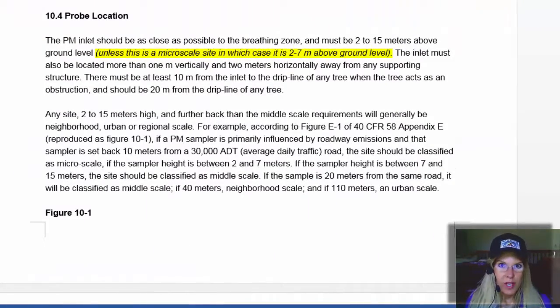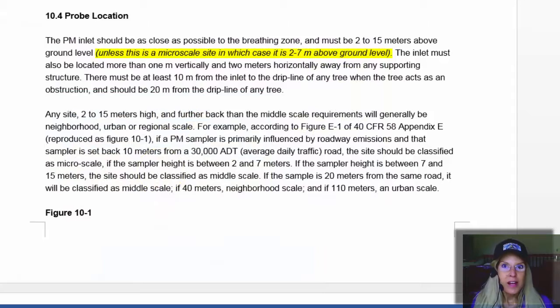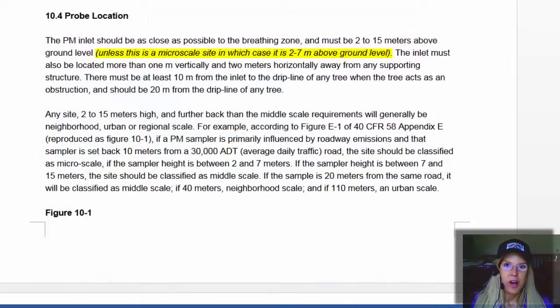So now we have to talk about probe location. So that means that the actual inlet of your air sampler is not too close to like an exit flue of any sort of incinerator, any sort of boiler. It's not too close to even a parking lot, for example, where cars could idle. It's not too close to the ground. So let's look up what the requirements are there.